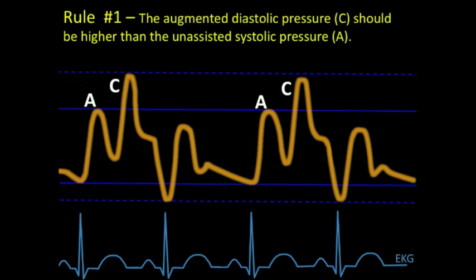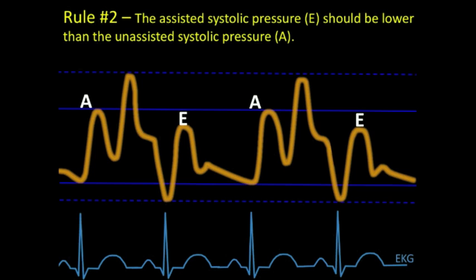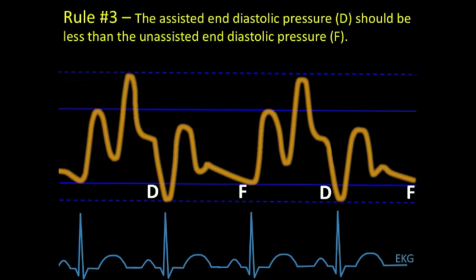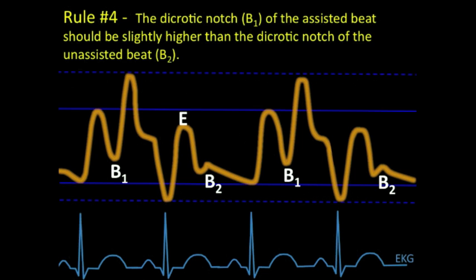There are four rules to remember. Rule one: the augmented diastolic pressure should be higher than the unassisted systolic pressure. Rule two: the assisted systolic pressure should be lower than the unassisted systolic pressure. Rule three: the assisted end-diastolic pressure should be less than the unassisted end-diastolic pressure. Rule four: the dicrotic notch of the assisted beat should be slightly higher than the dicrotic notch of the unassisted beat. The curve in our example meets all four criteria, confirming the balloon pump was properly positioned and optimized.